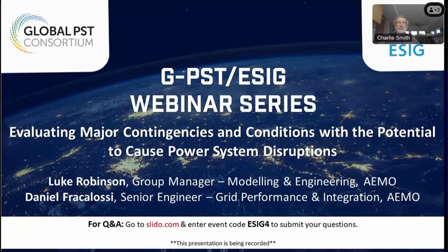So we do have a connection process where individual plants as they connect are tested and ensure that they don't cause additional harm, and they have the requirement to self-remediate, so provide their own system strength in an area. But if we have existing coal-fired or synchronous generation that retires, then we might see a reduction in system strength across the grid. So it's definitely an issue that we're looking at, and one that we may have to make whole of system recommendations as part of this general power system risk review, where we might need to fast track installation of synchronous condensers to make sure that we've got the required system strength so that the IBR will operate as expected.